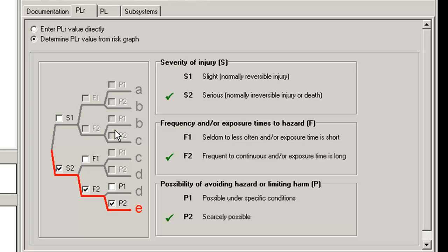The main purpose of SISTEMA is to determine the performance level of a safety circuit and confirm that it is at least as good as the performance level required of a given safety function. Note that in SISTEMA, the default PLR is PLE.